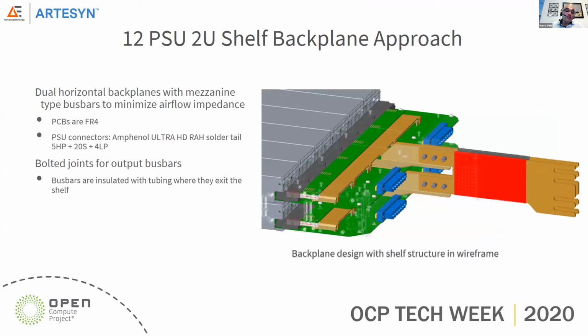I want to point out a unique feature of this Artesyn design where we use dual horizontal back planes with mezzanine type bus bars. These two unique bus bars allow for airflow, minimizing airflow impedance so that there can be maximum airflow. That is a unique feature of this design.